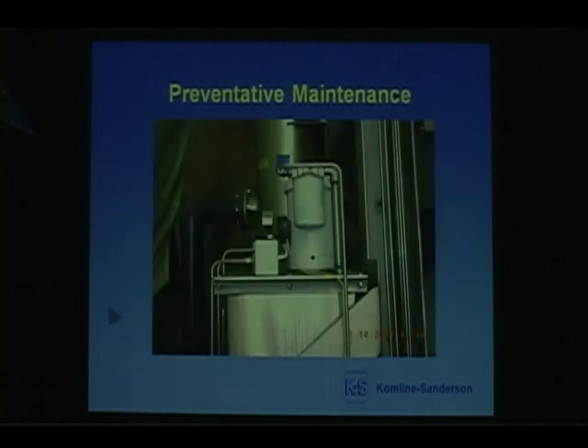Your hydraulic power unit filter: whatever the manufacturer recommends, I believe it's after the first 250 hours, you remove the filter, drain the oil, and replace.